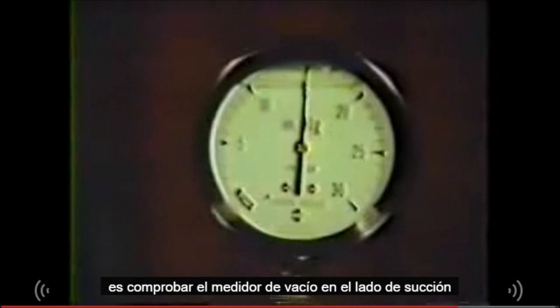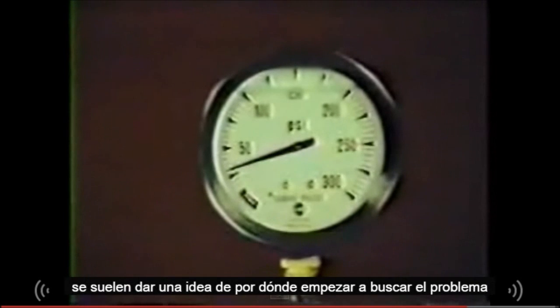If trouble does develop, one of the first steps toward finding the difficulty is to check the vacuum gauge in the suction side and the pressure gauge in the discharge side of the pump. Readings on these gauges will often give a clue as to where to start looking for the trouble.